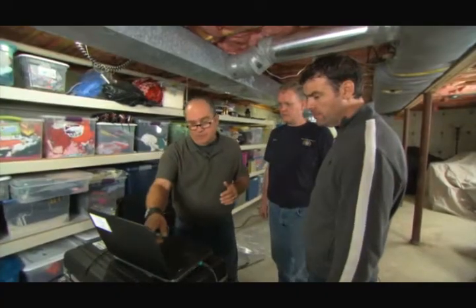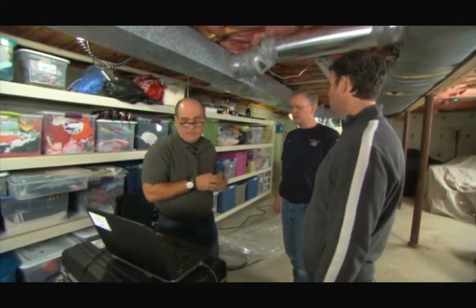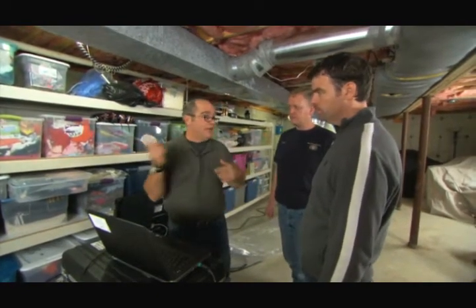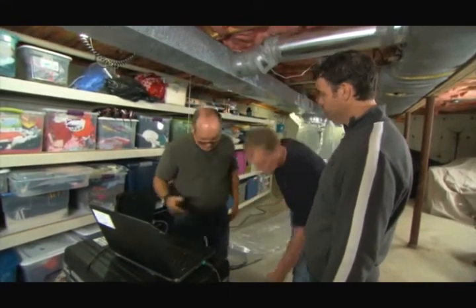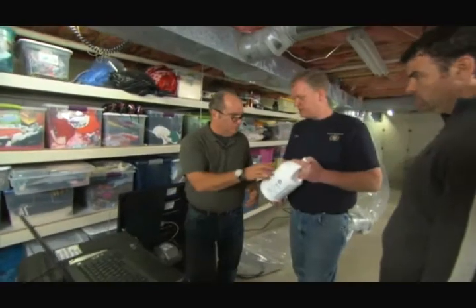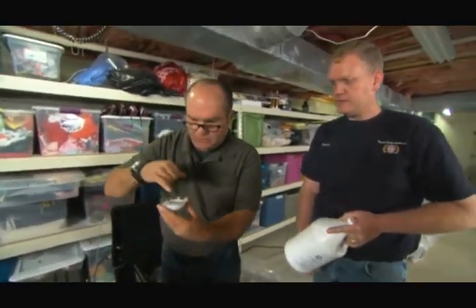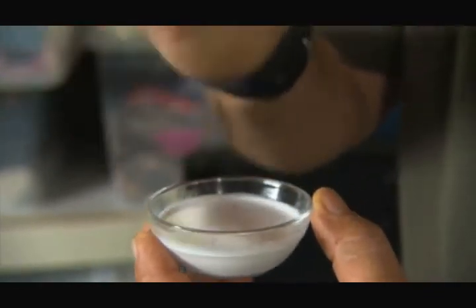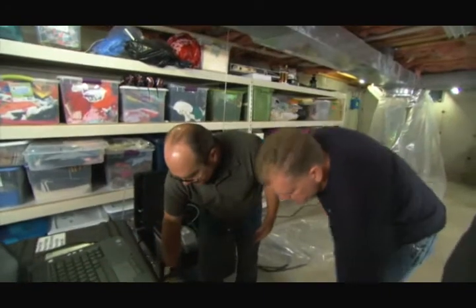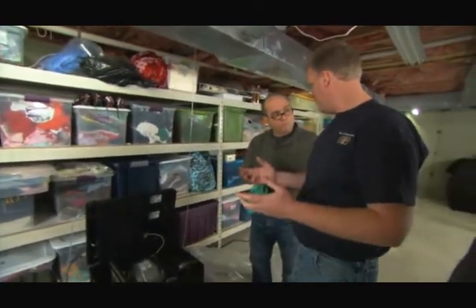Wow. So let's do the math. 307 CFM, this is a 4-ton system. That's like just under 20%, right? Correct. Okay. So 20% is not coming back to be reheated. You're heating your neighbor's house. It's unbelievable. All right, so how do you seal the ducts? Well, first we're going to start with the sealant. So that's a liquid. Is that what this is here? It is. Okay, sort of milky, sort of rubbery. Okay. So great. How do you get it into the ductwork? It's a liquid. So in order to seal the ducts, we need to do it as an aerosol.